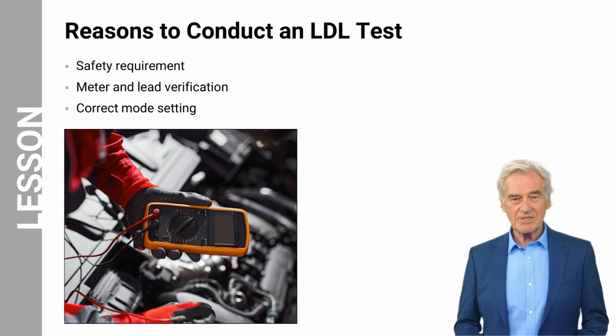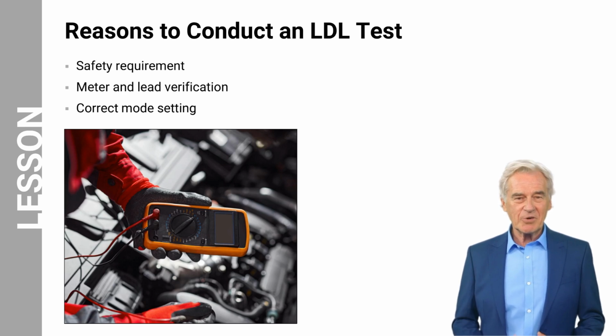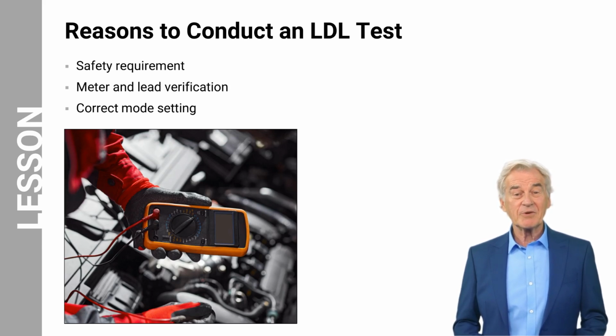Next is the importance of setting the multimeter to the correct mode. A digital multimeter set to AC voltage can give false readings on HV direct current, DC, circuits, potentially leading to a mistaken belief that the system is discharged when it's not. An LDL test helps verify that the meter is set correctly and provides reliable measurements. This emphasizes the importance of using appropriate HV testing equipment and following proper procedures.